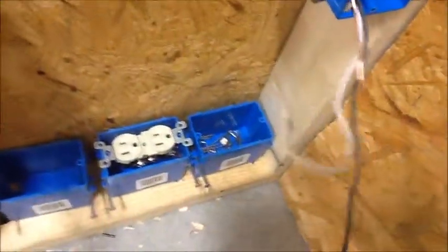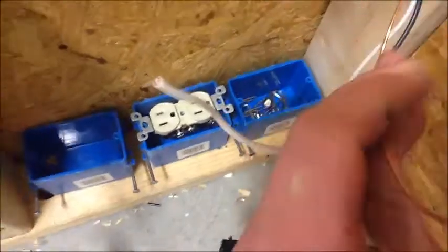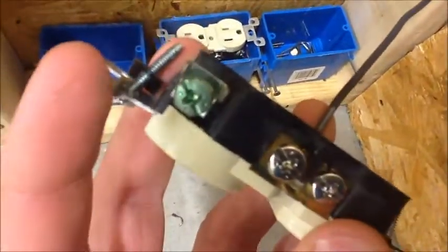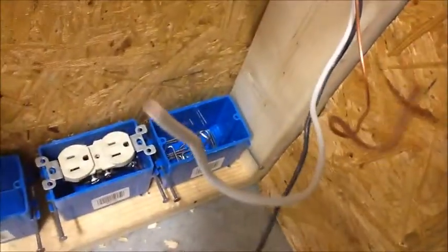To repeat this process, put the white conductor on the left side of the receptacle on the silver screws, and the green or bare copper ground wire on the green screw of the receptacle, making terminal loops. Pretty simple. Say you have 2 cables running into your box, and you need to install one device in here. You're going to have to somehow make both these wires go on the device, and that's where pigtailing comes in.